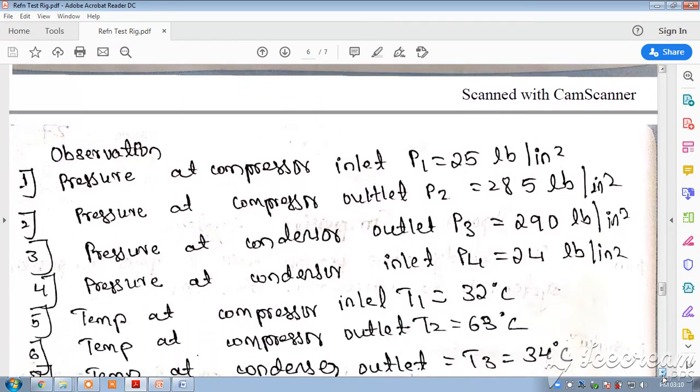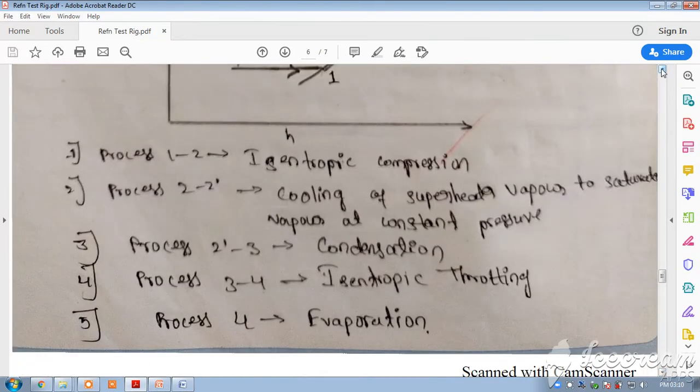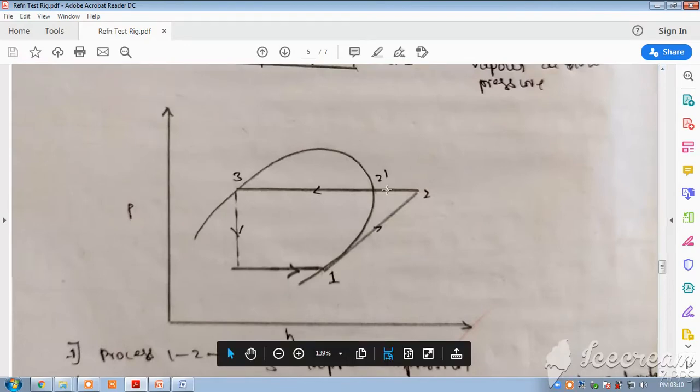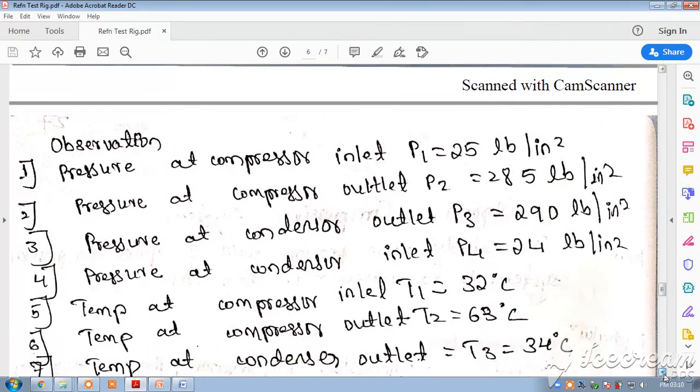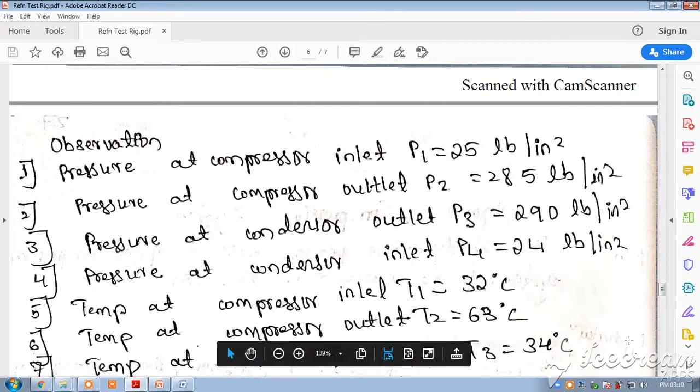We will take the readings - different readings of pressure as well as temperature. To find out this plot, to find out these points like 1, 2, 2 dash, 3, you need to have the pressure as well as the enthalpy. So what we are doing is finding out the temperature and pressure: pressure at compressor inlet, pressure at compressor outlet, pressure at condenser outlet, pressure at condenser inlet.